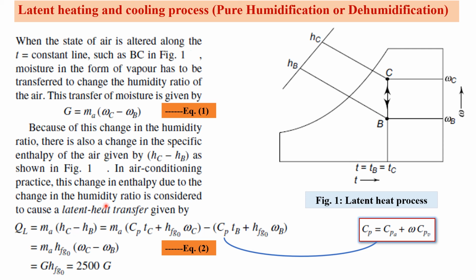Obviously, in humidification, the enthalpy of the air increases due to the enthalpy of the water vapor added. That is why this process is called a latent heat change. So now we can express this, the latent heat transfer QL is equal to Ma into Hc minus Hb. It is going to be expressed because Ma into Hc is nothing but Cp into Tc plus Hfg naught into omega C. Likewise, we can also express Hb in terms of this Cp and omega. So it's going to be Cp into Tb plus Hfg naught into omega B.